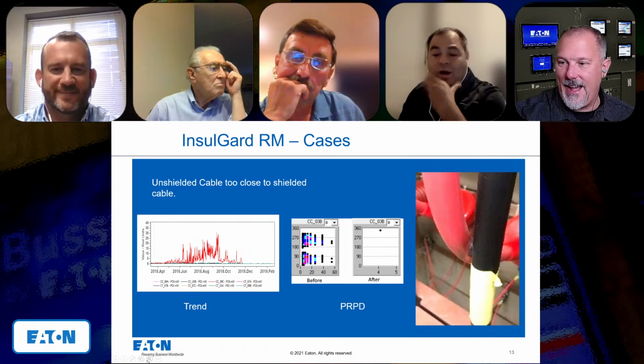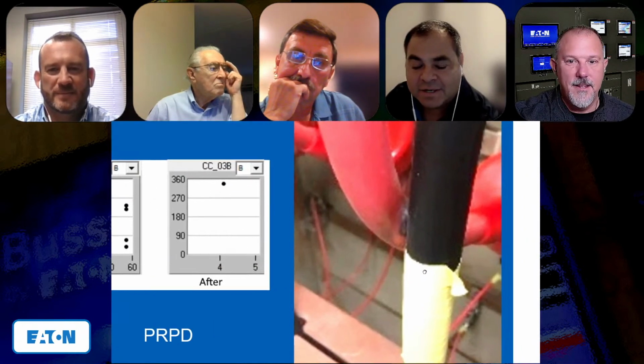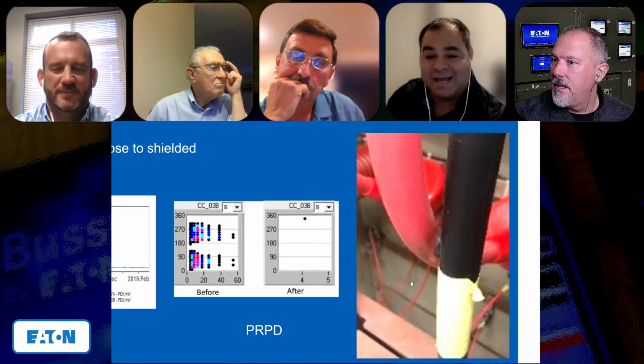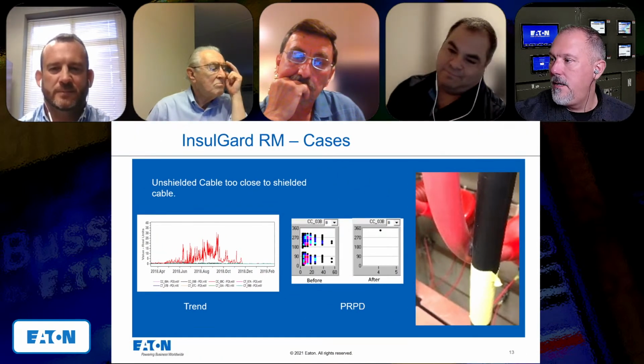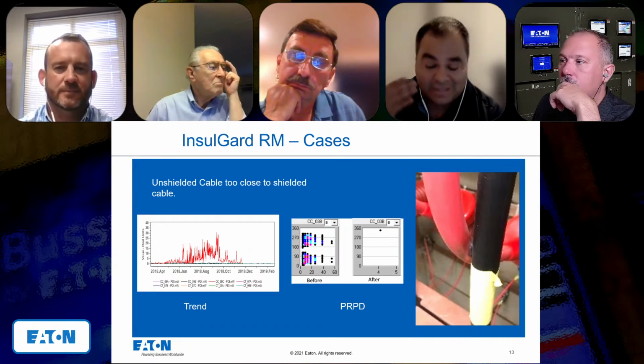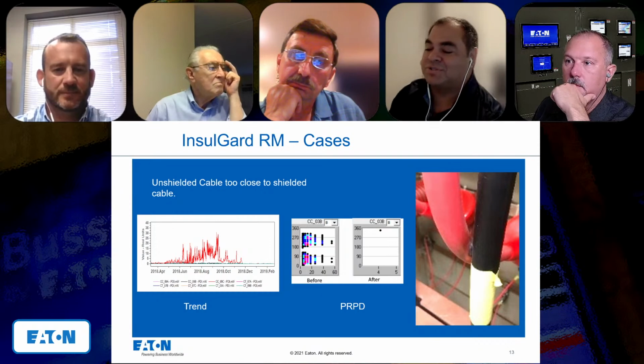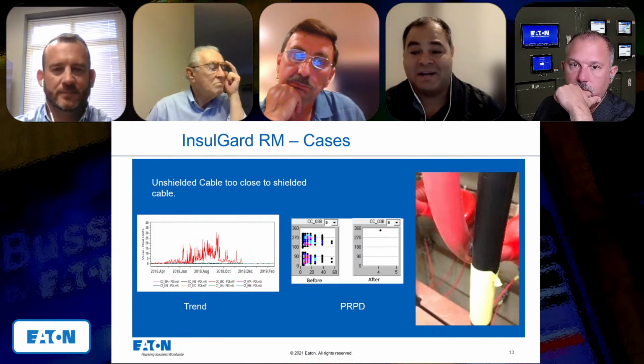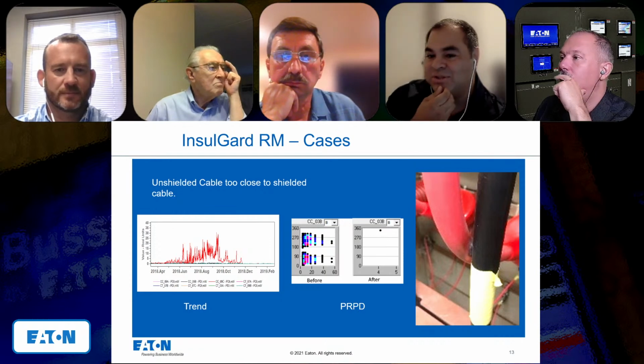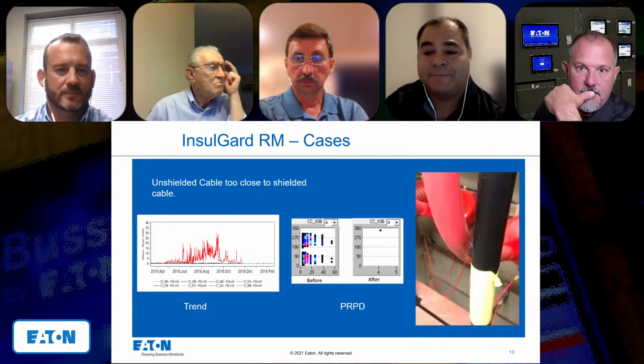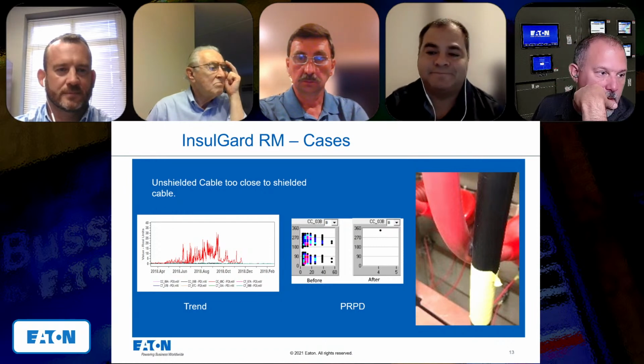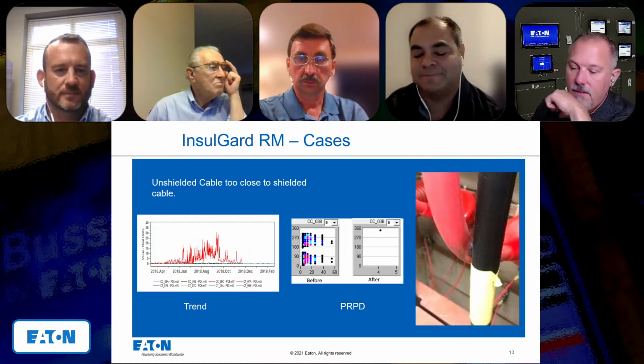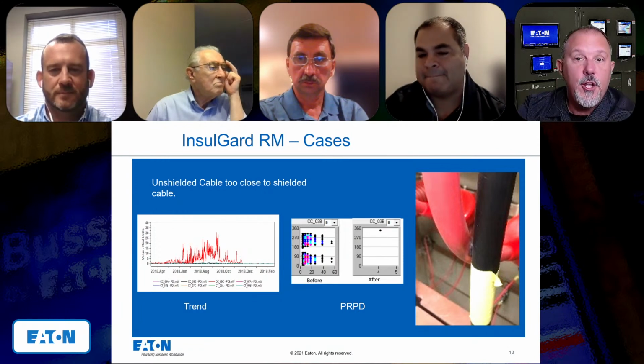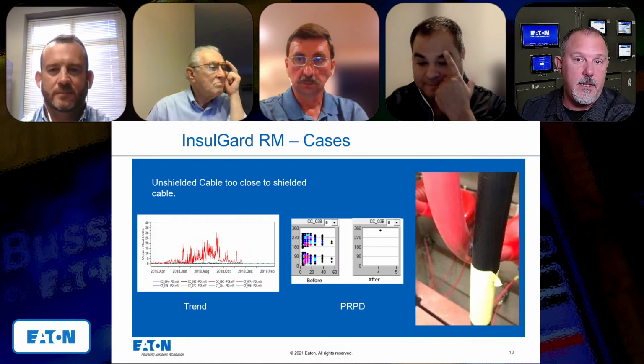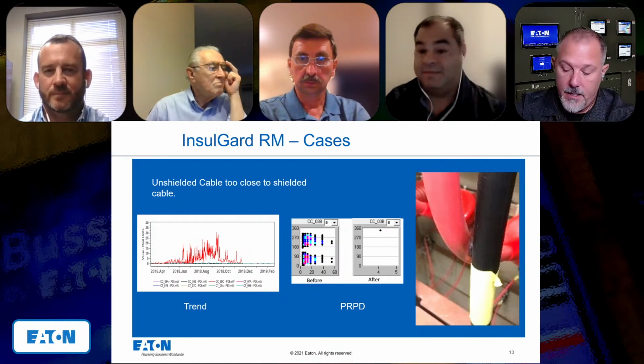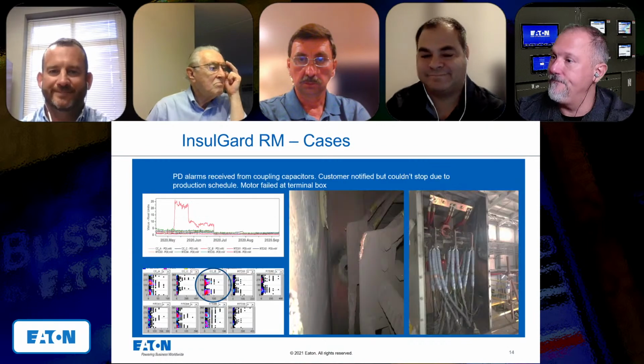Look at this case. This is a customer that was having alarms triggering, and we let them know, hey, you need to take a look at this information, you need to stop this switch. It's a switch gear. Finally they asked us to be there for the inspection, and we found this. So PD was really occurring there, and we caught it in time. That was a success story. So they didn't have a catastrophic failure, but if unattended, it could eventually have led to an unintended rapid disassembly in the field.